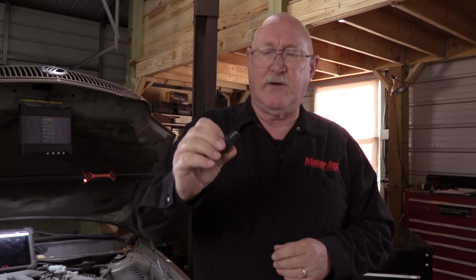So make sure that you know what that maximum input value is for your scope. Some older ones are around 50 volts. Most of the newer stuff is around 200. And be on the safe side. Use a device called an attenuator like this one, installed in line with the meter lead or the scope lead. Now what this does is it steps the voltage down going into your scope by a factor of 10 or 20 to 1, depending on the attenuator. This protects your scope without affecting the pattern that you see on your screen. Now, if you have the option, make sure you go to your probe menu and select the appropriate attenuator so that the voltage scaling is correct.